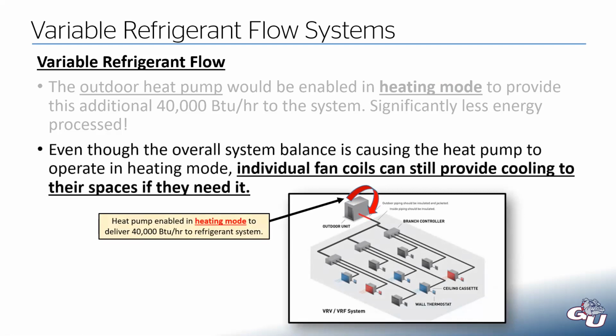And even though the overall system balance is in heating mode, so our outdoor unit is running in heating mode, that still means that all of our indoor fan coils can still operate in cooling mode. So just because our outdoor unit is in heating mode does not lock out cooling. And so we're still able to have those competing modes, where the conference room that's loaded up can get the cooling it needs, even though the rest of the system is operating in heating mode.